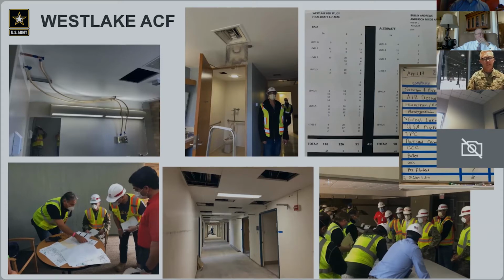Westlake didn't have as good bones as Metro South Hospital, so in the upper left there we're bringing in oxygen and vacuum in a far more expeditionary way, just getting it in there as quickly as we can. You can see the flex hoses coming into those outlets. In the center picture, a different method for creating negative pressure - we're using the existing exhaust systems in each room and balancing the HVAC systems to pull more air out of the room through that exhaust system more effectively to create negative pressure.